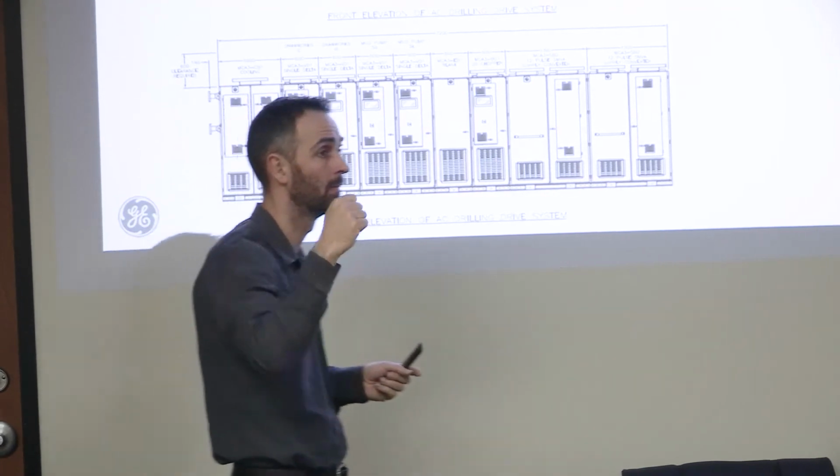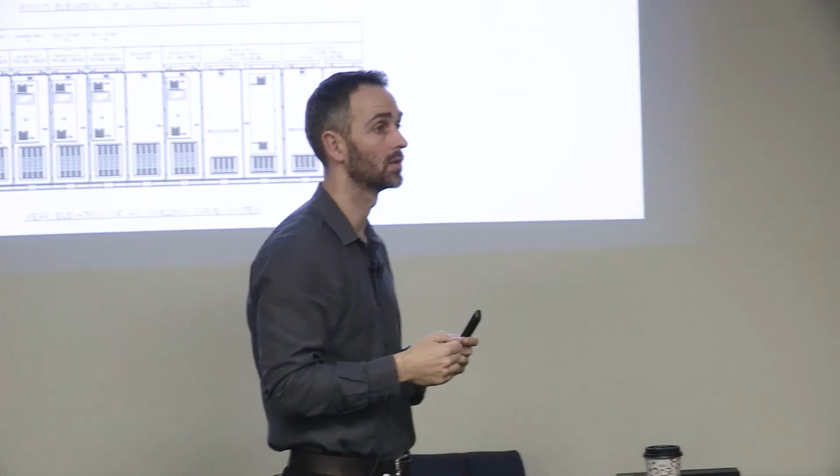In between them there is a manual DC isolator. What we would recommend in most practices is for that DC isolator to remain open and only ever close when we need to maintain drilling operations if you lose half the board, as the bottom line. If you lose half of your generation capability, we want somebody to go and switch that DC link, connect it to the other generators, and carry on as normal. But generally, in 99% of cases, that is an offload system that will require you to shut down that side of the bus, and close it.